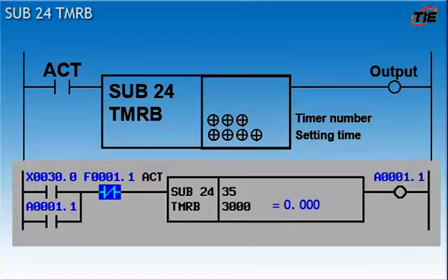This timer behaves just like the TMR variable timer. This timer does not have an accuracy level and can be set up to around 546 minutes. When the ACT signal command goes high, the timer will begin to time out. Once it's timed out, it will turn on the output. This output will stay on as long as the ACT command signal is high. If ACT goes low for even one scan of the ladder, the output will turn off and the process starts over again.